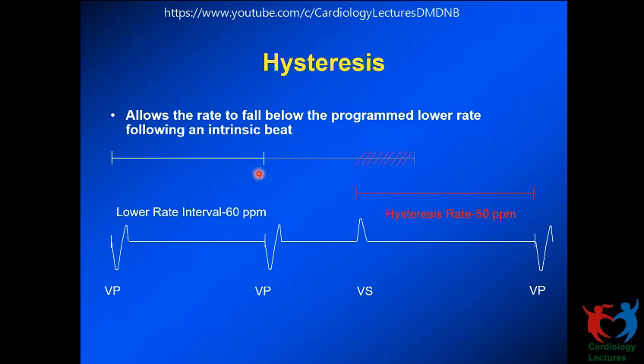Then we can program the hysteresis function on. When we turn the function on, we program two settings. One is the lower rate, which is in this case 60 beats per minute. And we also program a hysteresis rate, in this case 50 beats per minute. When we program this on, every time the pacemaker paces, it starts a lower rate interval and paces at the end of the lower rate interval. Now it started a clock again.